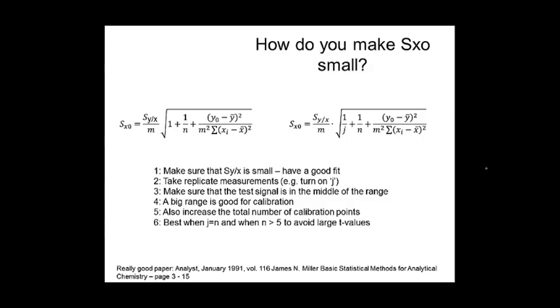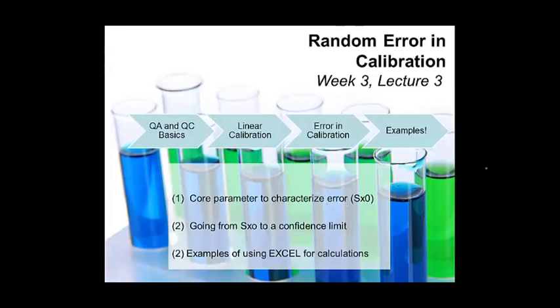However, as you can also see, you can make the square root component of this equation small by, for example, taking replicates. The other thing you can do is it's helpful if your signal is actually in the middle of your calibration range. So if Y zero minus Y bar is zero or close to it, then that third term drops out completely. The other thing you can do is make SXX very big. If that's a very big value, then one over a big value is close to zero. There's a really interesting paper I give here that goes through this, and they had a really great proof that you actually optimize your SX zero when J is equal to N. And you really want an N greater than five to avoid your T values being too large when you turn them into confidence limits.